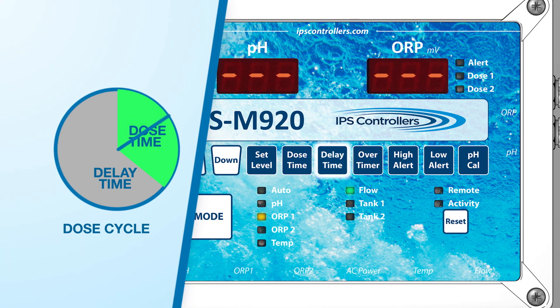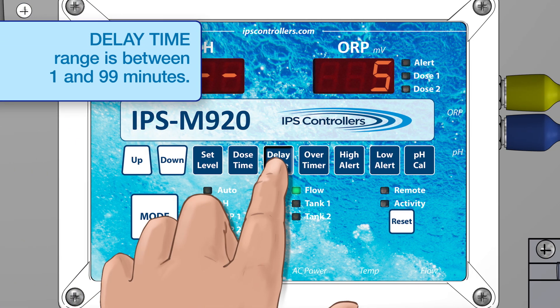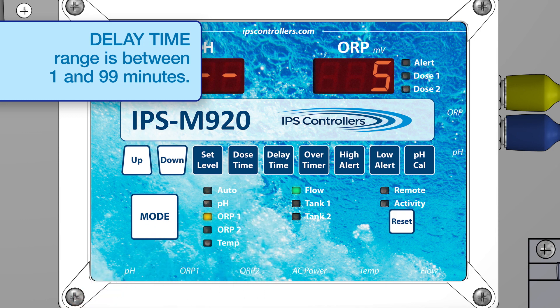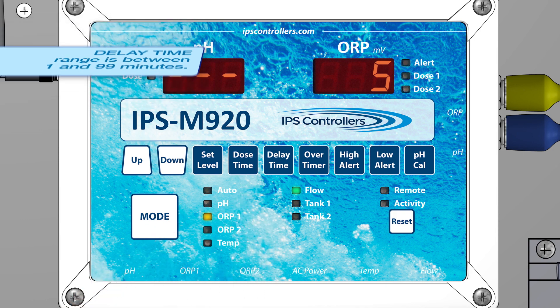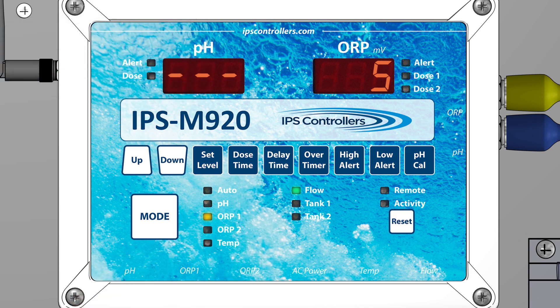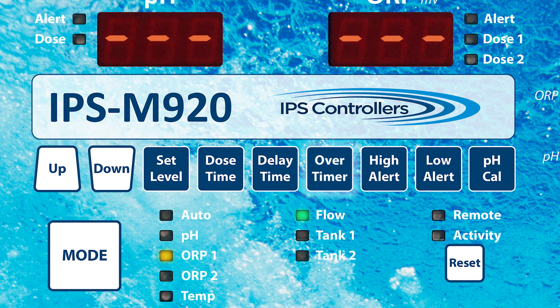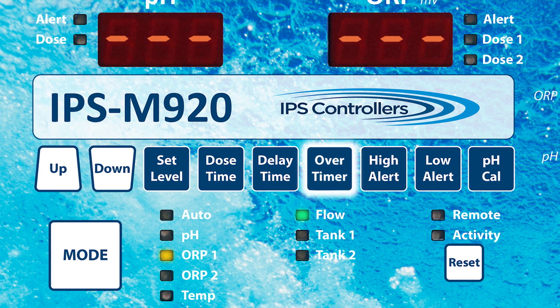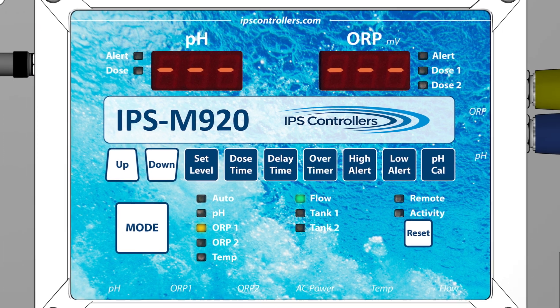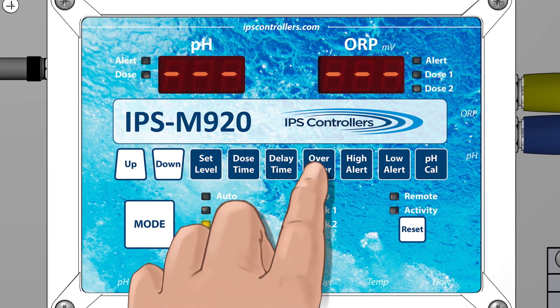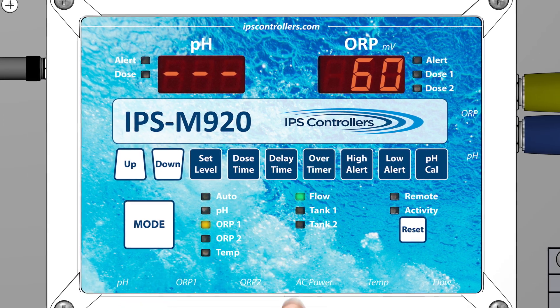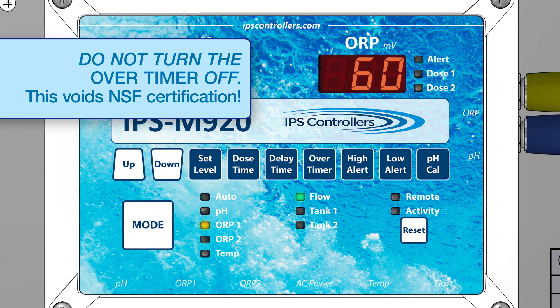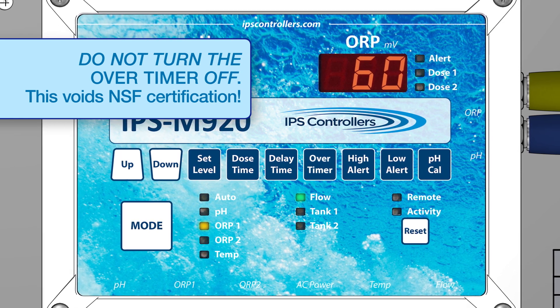The delay time is how long the controller waits between dose time cycles. The delay time function in the ORP mode is the same as in the pH mode — the 5-minute delay should be sufficient. The Over Timer functions in the ORP mode are the same as in the pH mode. The Over Timer is a safety mechanism; do not turn the Over Timer off.